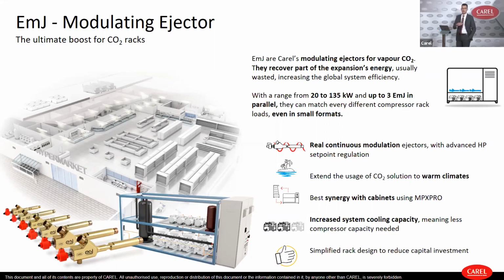At the same time, this is a vapor ejector, so it's very good for warm climates. And we have a special synergy with cabinets in order to match the operating conditions of the racks with the conditions that are happening on the cabinets and cold rooms sides. Another important benefit is that by fitting ejectors in the rack, with high temperature conditions, the cooling capacity of the rack can be boosted, can increase because of the use of the ejector. And in the next slide, I will explain why.